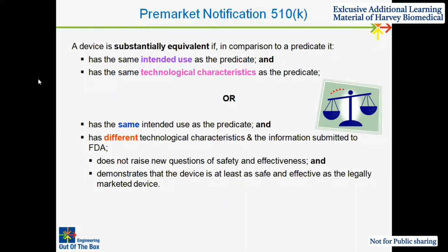Predicate means similar or has the same intended use, or the predicate has different technological characteristics, but the information submitted to FDA does not raise new questions of safety or effectiveness. It means any new question should not raise any safety and effectiveness concerns. Whatever the intended use and intended purpose, the safety and the performance should be similar. Then only will they call it a predicate. Demonstrate that the device is at least as safe and effective as legally marketed devices.